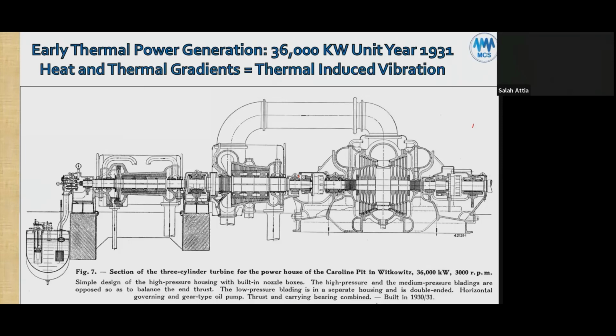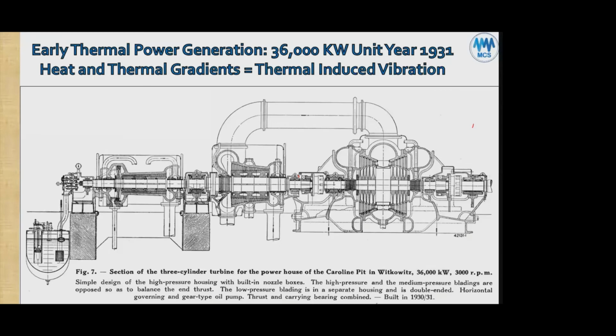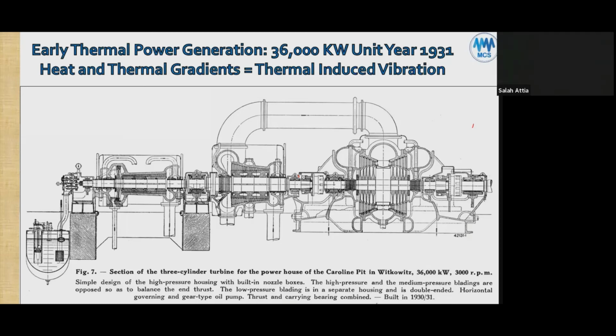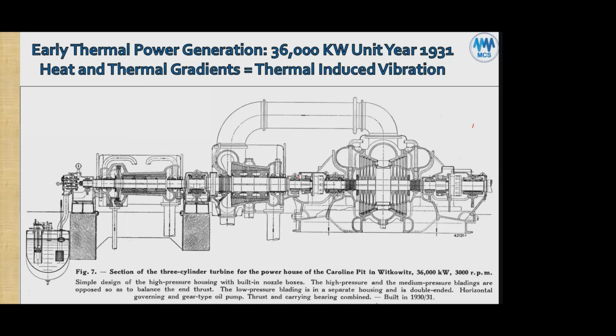Because I had a similar condition. Yeah, okay, I'm just calculating in my head. What he just mentioned in your explanation could happen when it's a high-speed turbine. But in my head, I was still stuck in power generation, 3,000 RPM. So if it's a high-speed turbine, whether it's driving a generator through a gearbox or a compressor or other drive, and it might be at 7,000 RPM normal, for example, or 8,000, then it has a tilting pad bearing, you said, right?